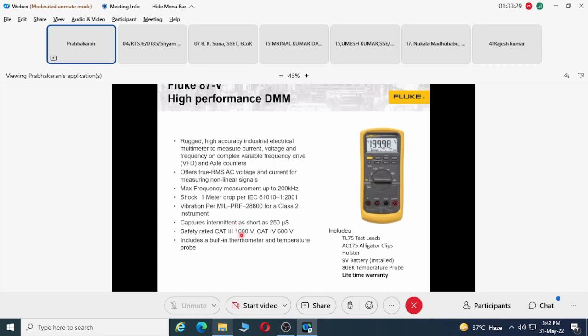Here you can see the safety rating has gone up, to category 3, 1000 volt. It can measure up to 1000 volts in category 3 rated conditions, or up to 600 volts in category 4 environments - that is how we recommend our instruments. It also comes with a range of leads, accessories, and a lifetime warranty.